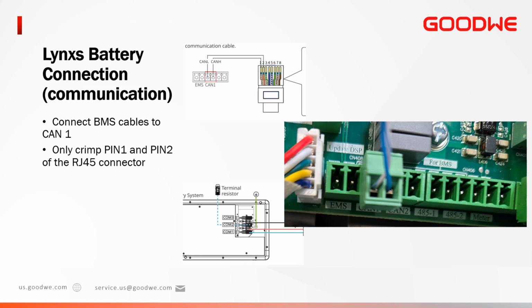Also, these inverter series are compatible with the LG battery and BYD battery. For these batteries, the communication wire connections are different than the Lynxs, so please make sure you follow the specific instructions from the manufacturer. Once we get through the commissioning part of this training, I will show you how easily you can check if the communication has been established between the battery and the inverter.